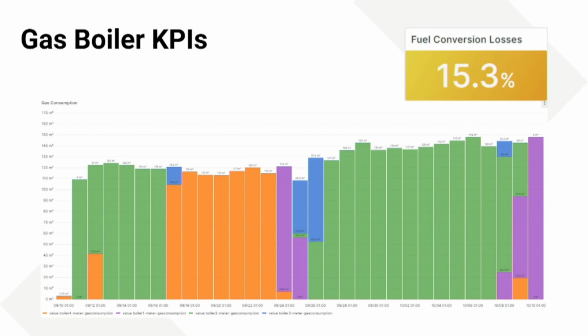Gas boiler KPIs. Fuel conversion efficiency. This can vary wildly, how the boiler is actually set up, regardless of what the network's doing. This is live gas consumption KPIs from a site with 4 boilers, where the efficiency notably changes as you rotate between boilers. So this kind of dashboard actually tells the operator of the site, it gives them the information. They go, why is boiler 2 running twice as efficiently as boiler 1?